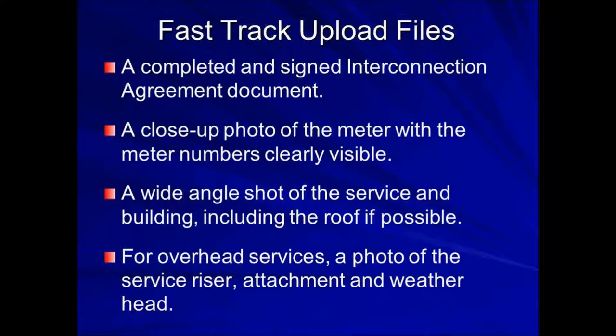It's a one-page deal for anything under 30 kW. You'd upload a close-up photo of the meter with the meter numbers clearly visible, a wide-angle shot of the service and building including the roof if possible, and for overhead services, a photo of the service riser above the roof showing the attachment and weatherhead wires.